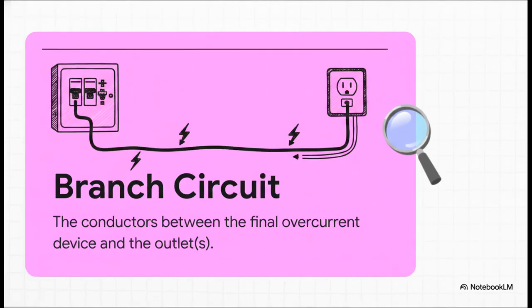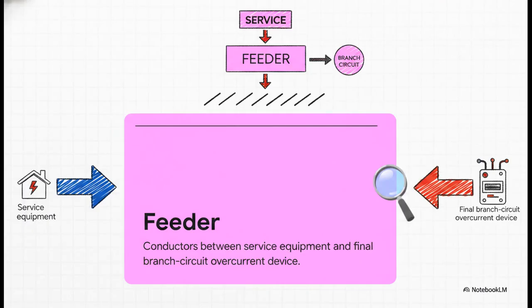Okay, let's follow the flow of power for a second. A branch circuit is essentially the final leg of the electrical journey. By definition, it's the conductors located between the final overcurrent device, like that last circuit breaker in your panel, and the actual outlets where the power is finally consumed. Building right off that idea, if the branch circuit is the final leg, then the feeder is basically the middleman. A feeder is made up of the conductors between the service equipment, where power actually enters the building, and that final branch circuit overcurrent device. The code is just meticulously charting out the entire hierarchy of power distribution.